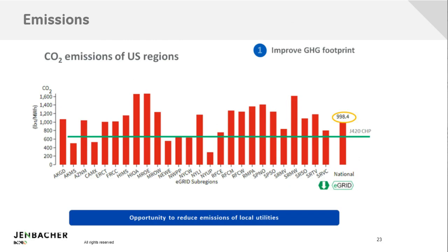Moving on with emissions, this chart shows the greenhouse gas improvement for CO2 specifically across U.S. regions. The horizontal axis shows all the grid subregions across the United States, and the vertical axis is pounds of CO2 per megawatt hour produced. Compared to that is the green line, one of our model J420 gensets running on natural gas in a CHP application. You can see the CO2 emissions are considerably lower than the majority of what was typical in each region—there are one or two, maybe four regions lower than the 420, but the majority are considerably higher.